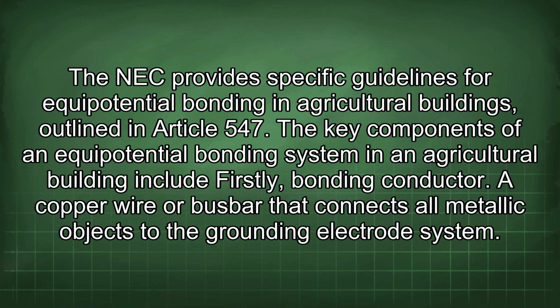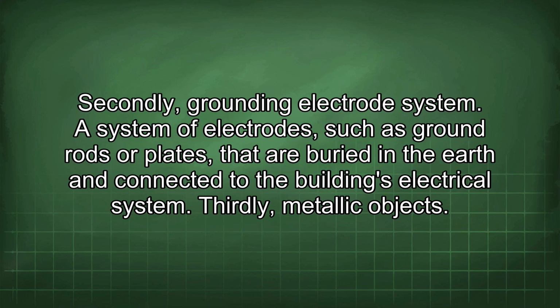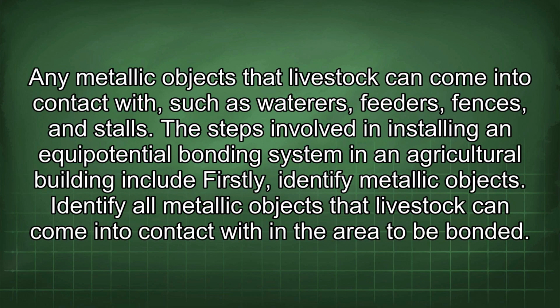The key components of an equipotential bonding system in an agricultural building include, firstly, bonding conductor, a copper wire or busbar that connects all metallic objects to the grounding electrode system. Secondly, grounding electrode system, a system of electrodes, such as ground rods or plates, that are buried in the earth and connected to the building's electrical system. Thirdly, metallic objects. Any metallic objects that livestock can come into contact with, such as waterers, feeders, fences, and stalls.